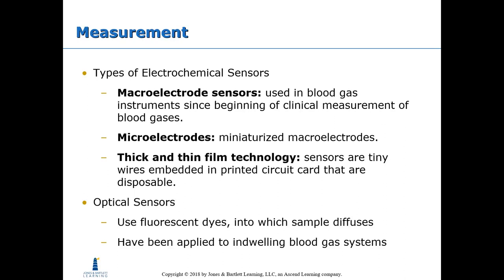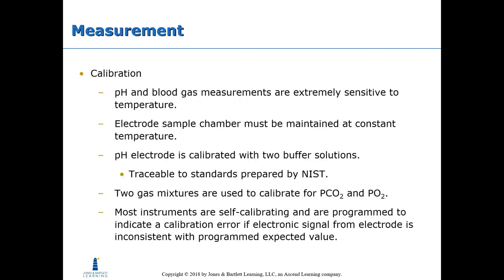Types of electrochemical sensors: macro electrode sensors have been used in blood gas instruments since the beginning of clinical blood gas measurement. Micro electrodes are miniaturized macro electrodes. Thick and thin film technology uses sensors — tiny wires embedded in a printed circuit card — that are disposable. Optical sensors use fluorescent dyes into which the sample diffuses and have been applied to in-dwelling blood gas systems. Calibration of pH and blood gas measurements is extremely sensitive to temperature, so the electrode sample chamber must be maintained at constant temperature. The pH electrode is calibrated with two buffer solutions traceable to NIST standards; two gas mixtures are used to calibrate for pCO2 and pO2. Most instruments are self-calibrating and programmed to indicate a calibration error if the signal from the electrode is inconsistent with the programmed expected value.